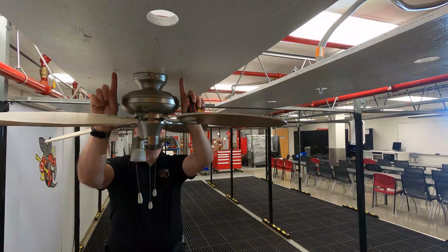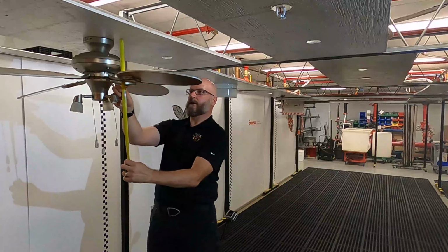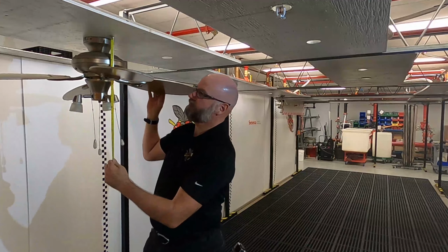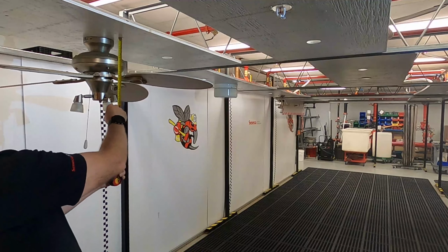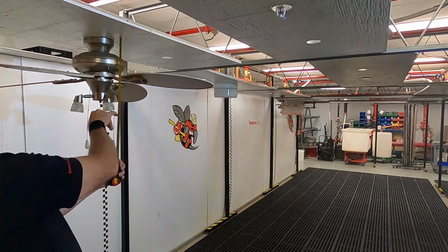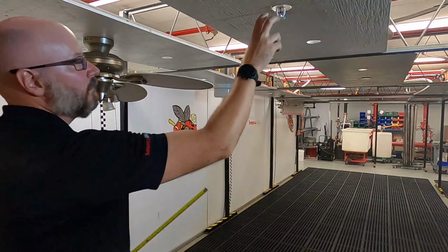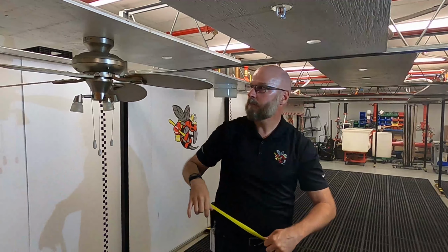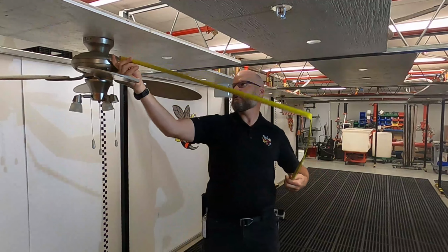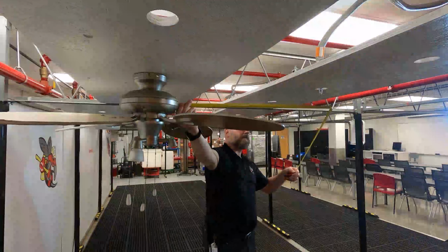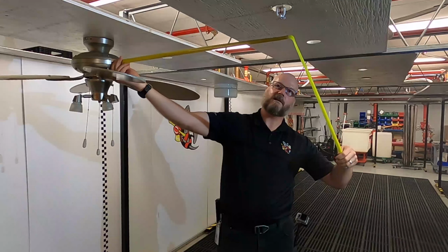So think of it as being straight down, straight across, and if I go from that, we've got a base dimension from the ceiling down to where the lights would be of approximately 11 inches. 1 inch down for the deflector plate, and we go from the edge of the obstruction to the center of the sprinkler head deflector, which would be 29 inches this time.